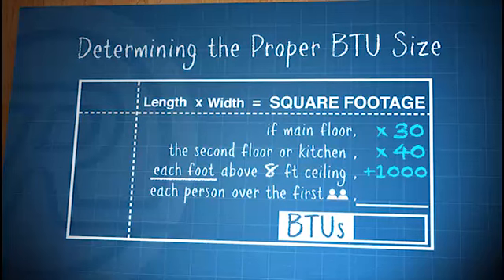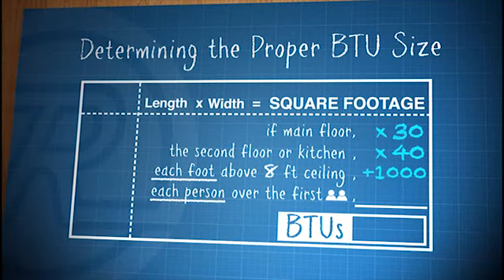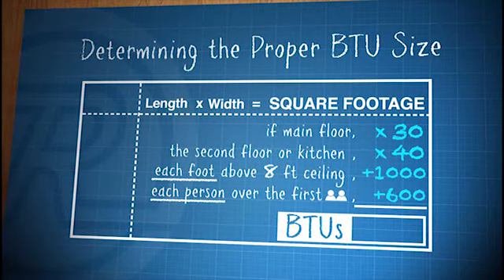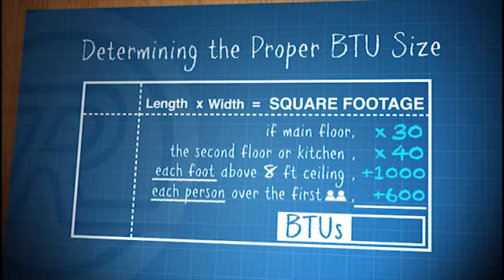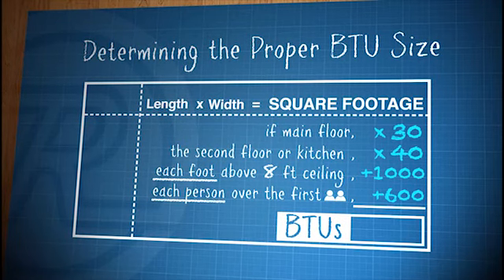You should also take into consideration the number of people in the room. For each person over the first 2 individuals, you must add an additional 600 BTUs to your formula.